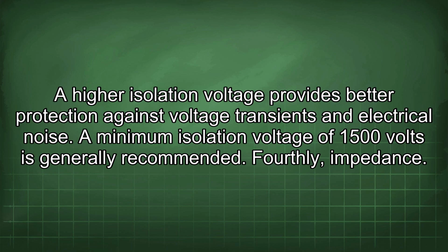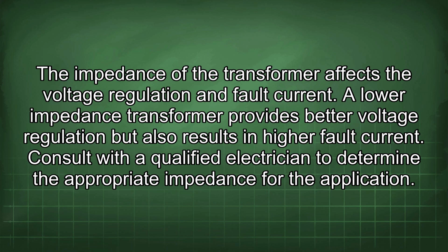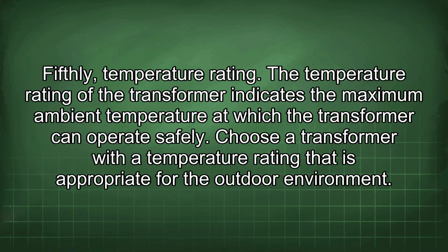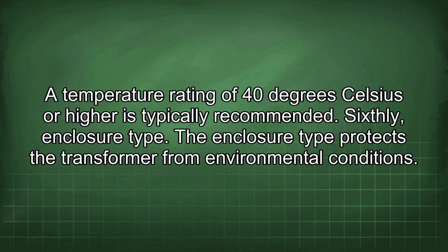Fourthly, impedance. The impedance of the transformer affects the voltage regulation and fault current. A lower impedance transformer provides better voltage regulation but also results in higher fault current. Consult with a qualified electrician to determine the appropriate impedance for the application. Fifthly, temperature rating. The temperature rating of the transformer indicates the maximum ambient temperature at which the transformer can operate safely. Choose a transformer with a temperature rating that is appropriate for the outdoor environment. A temperature rating of 40 degrees Celsius or higher is typically recommended.